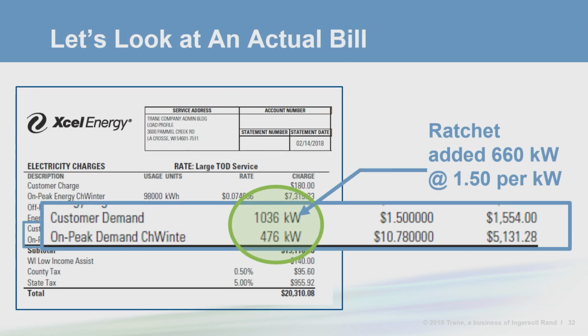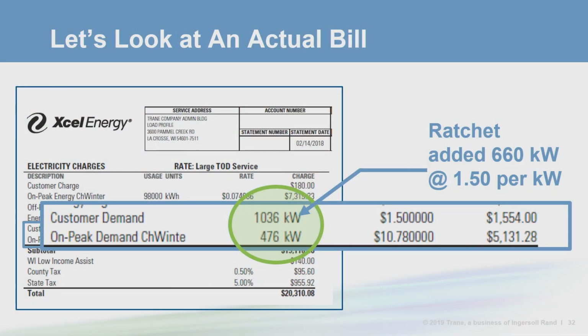Ratchets are very common in utility rates. I would say that over half of the nation's utilities in all regions of the country have them, and they're impactful. In this case, the ratchet adds 660 kW to the customer demand line item, and at $1.50 per kW, it costs this customer nearly $1,000 here in this 1 month alone. So, when you're designing air conditioning systems, even in colder climates like La Crosse, Wisconsin, you need to be mindful of those ratchet costs that can come even when the AC system will be idle all winter.